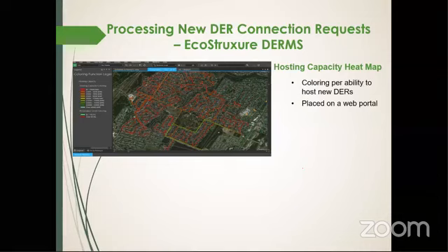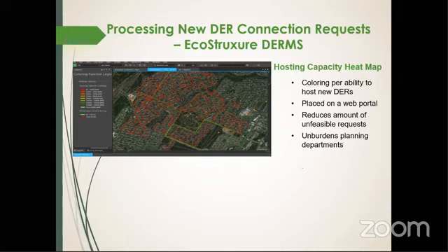Now, if I'm the customer and I want to connect, for example, a 10 megawatt PV farm at a specific location, without this heat map I would need to send the request to the utility. With the heat map, I log into the utility's web portal and see that only 800 kilowatts is allowed at this location. Of course, I'm not even going to send this request, it's fully unfeasible. I will think about changing the location and lowering my power. These heat maps on web portals significantly reduce the amount of unfeasible requests and unburden planning departments.